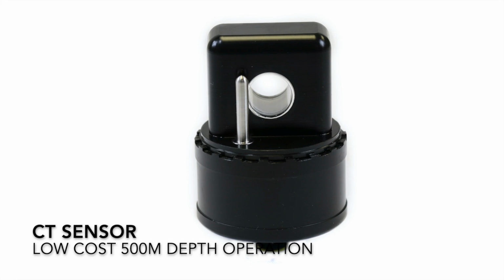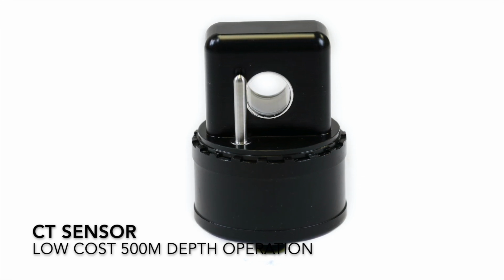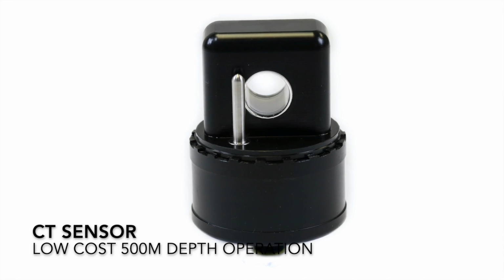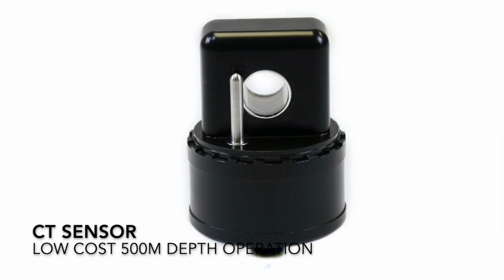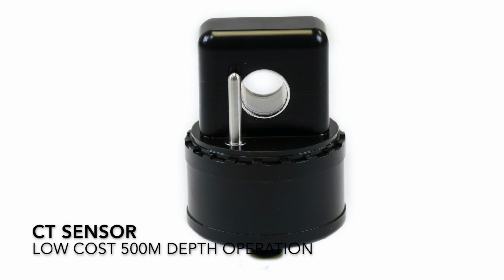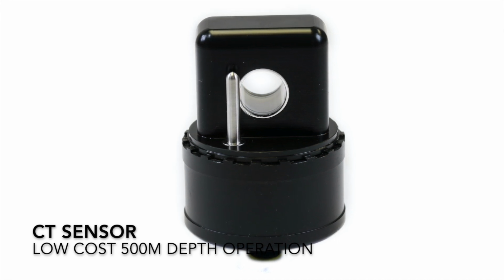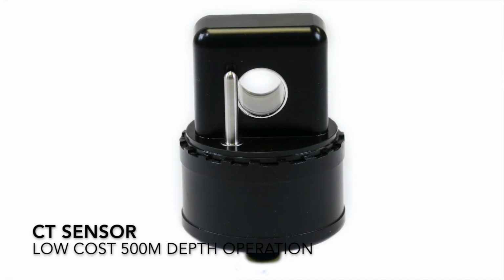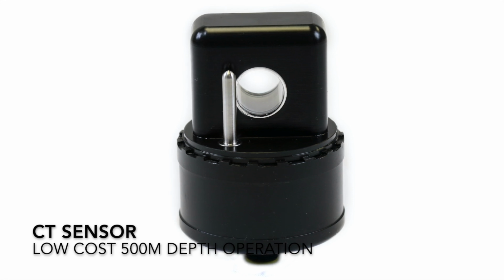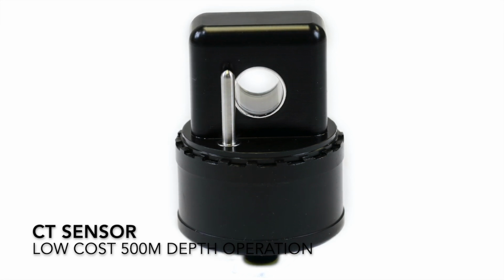We do offer a standard lollipop design conductivity cell which just has conductivity and temperature, and these are ideal for any measurement under 500 meters because they are very cost effective and can deliver enough accuracy within the first 500 meters of the ocean to be quite effective for measurement.